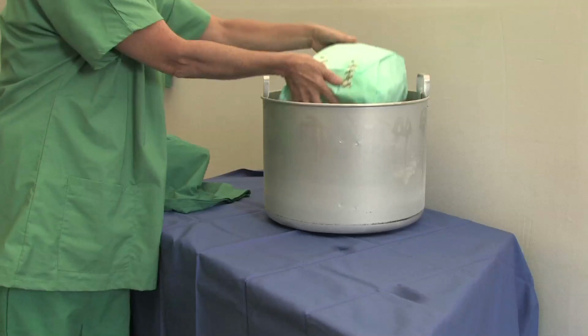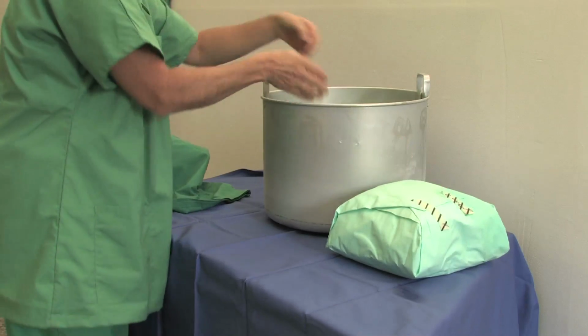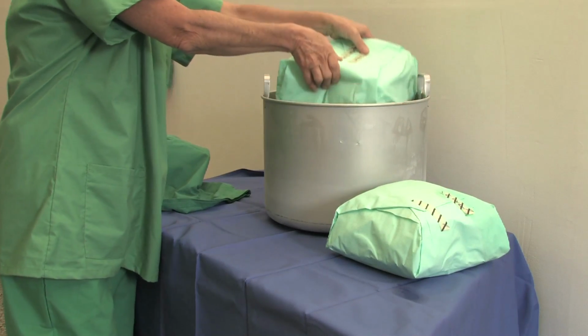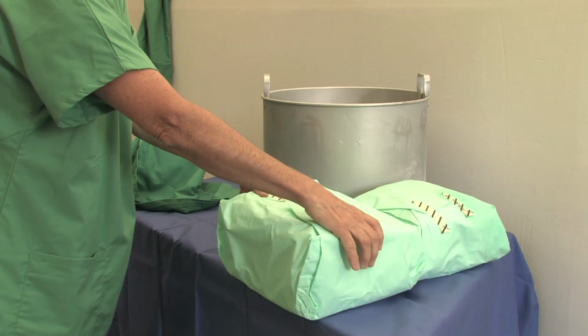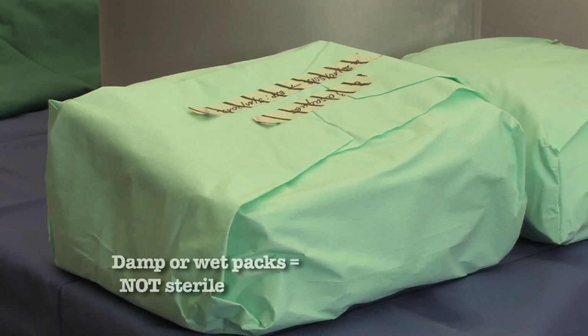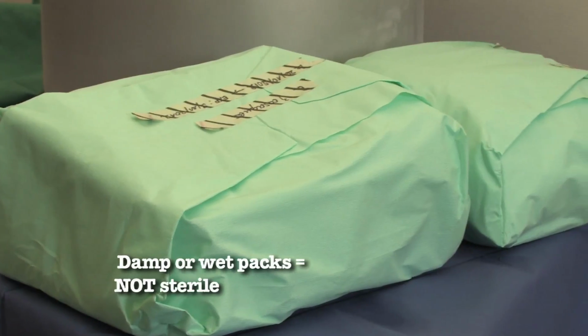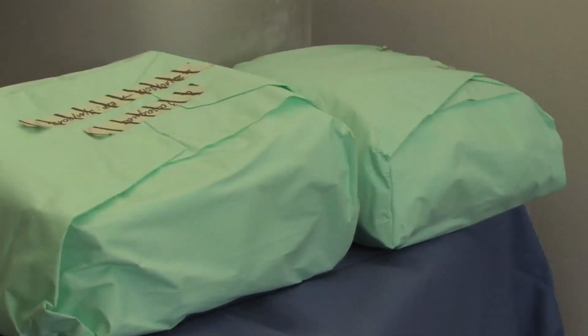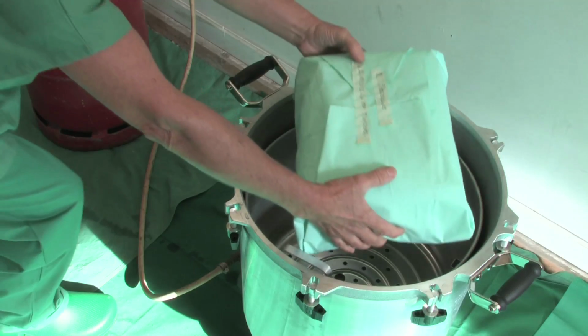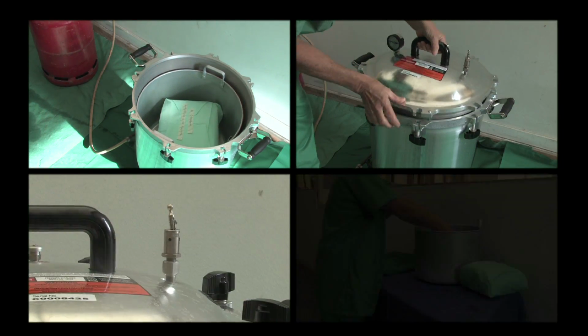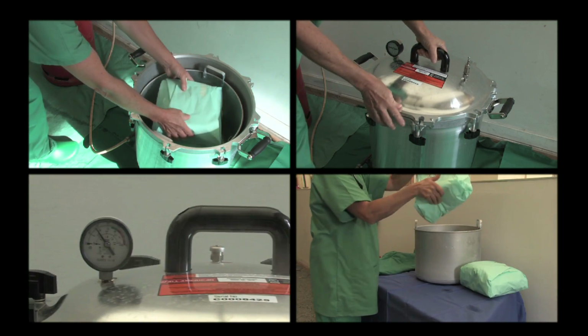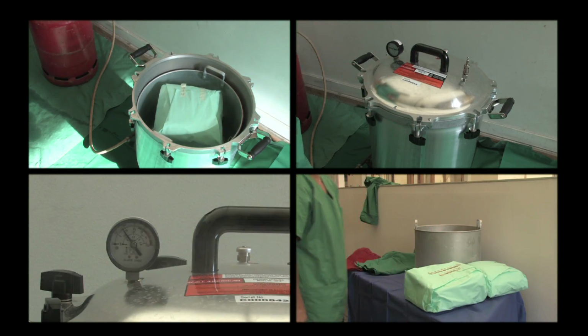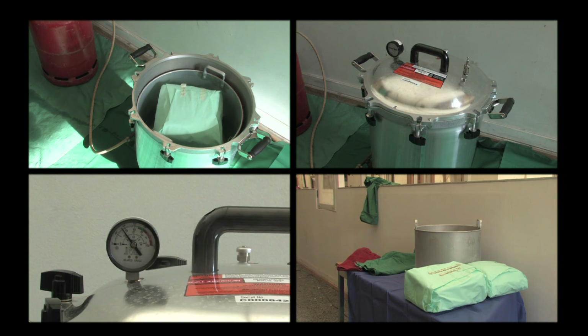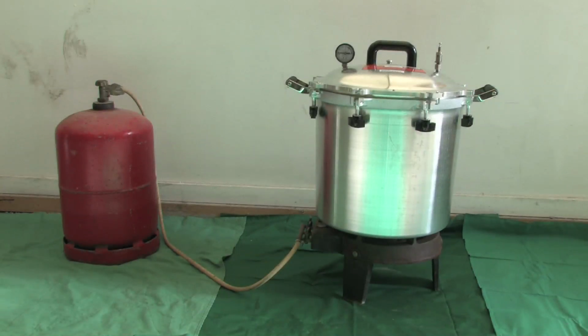The cooling system is very important because it allows the packs to dry. As a reminder, packs that are not dry when removed from the autoclave are considered non-sterile. They can be used right away, but must not be stored. In terms of quality assurance, therefore, it's very important to scrupulously follow the autoclave's use instructions and to use the equipment sterilized with this autoclave quickly, that is, with no storage period. The All-American is a very basic autoclave.